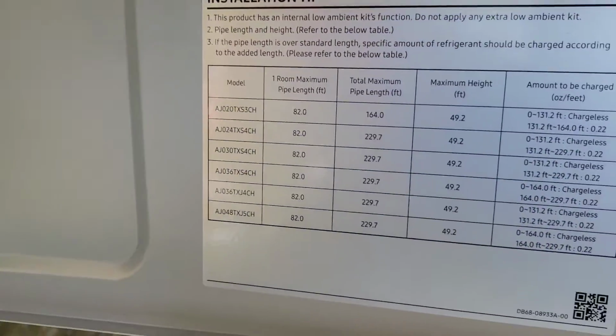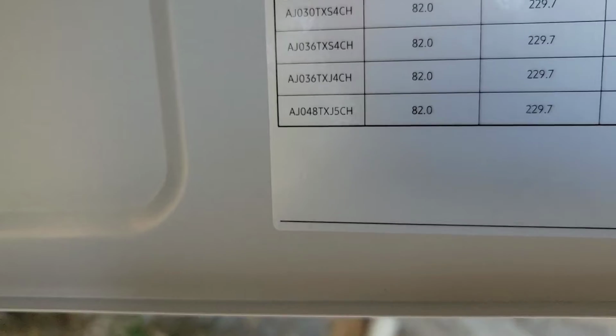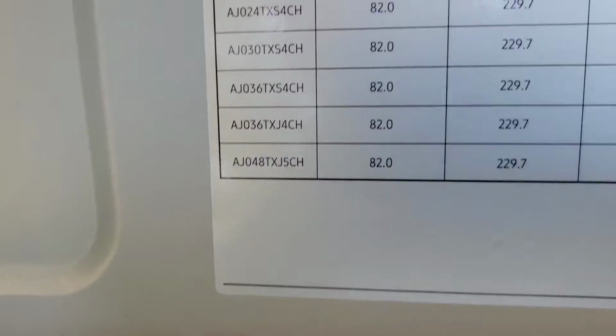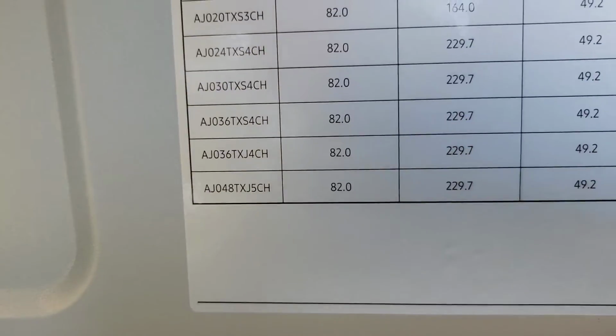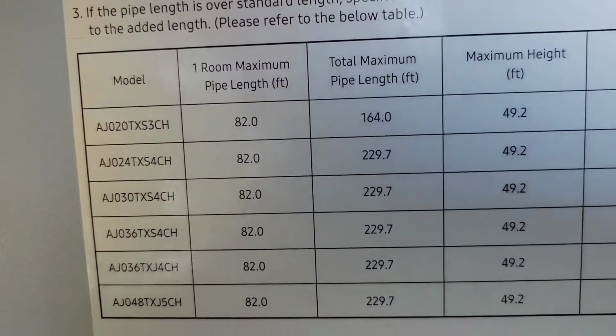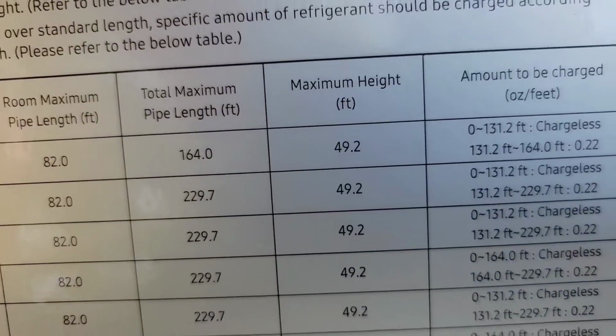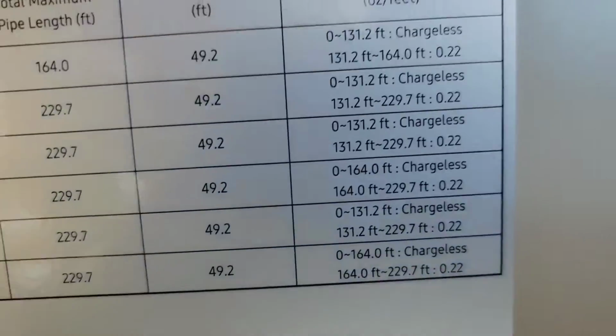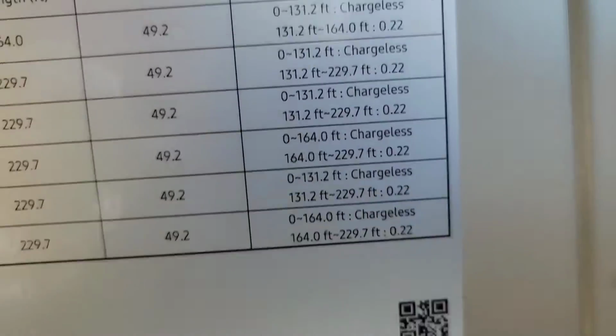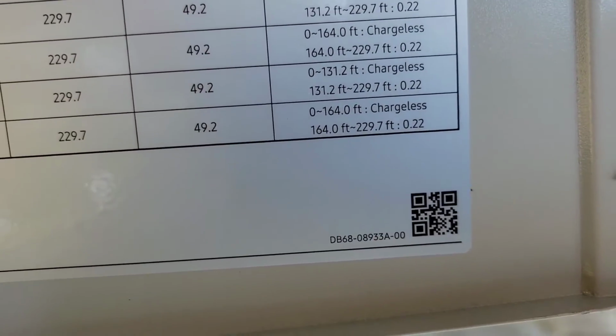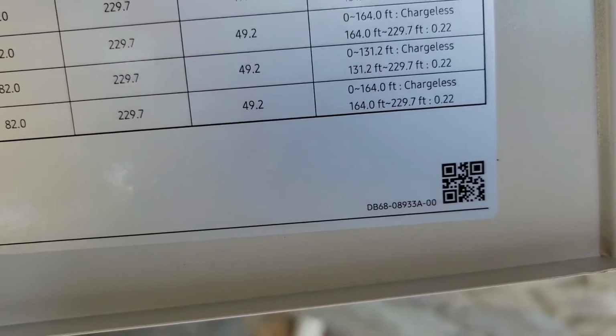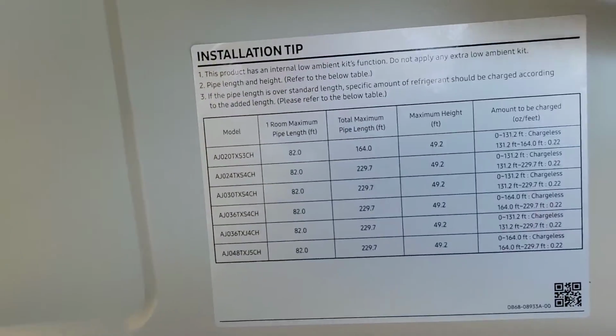All right, one more tip - I think I've gone over this in other videos. You find your outdoor unit model number, and it's going to give you 1 room pipe length maximum feet, total maximum pipe length feet, and maximum height is 49 feet, amount to be charged in ounces per feet. How you do that calculation, I've got a video on how to charge mini splits - you should check that out if you want to know more about this.